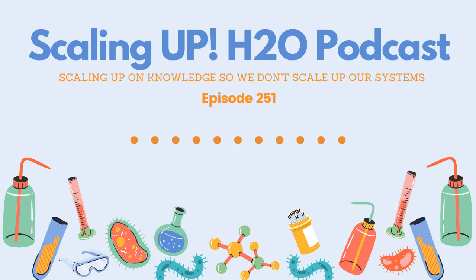Is the valve not adjusted properly? Maybe the valve just floated off or just disintegrated. I've seen that happen before. Maybe there is a situation where when the tower shuts off, there's a large volume of water that overflows the tower, and there's a design issue going on with that. Maybe they have a sand filter, and thank goodness they have a sand filter. Every single cooling tower should have a sand filter, but maybe it's not set up right on backwash. Maybe it's backwashing too often. Maybe it's allowing too much water to be bled out of the system and we're not able to concentrate up.